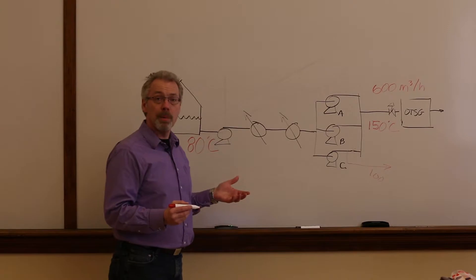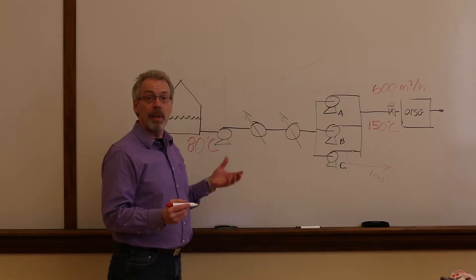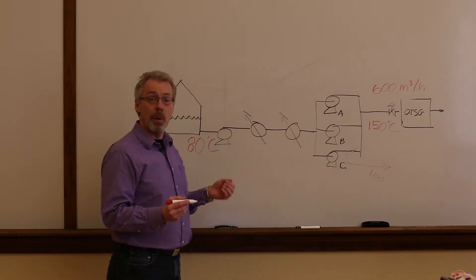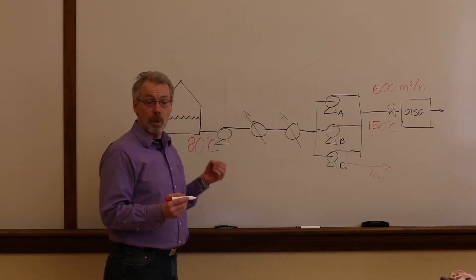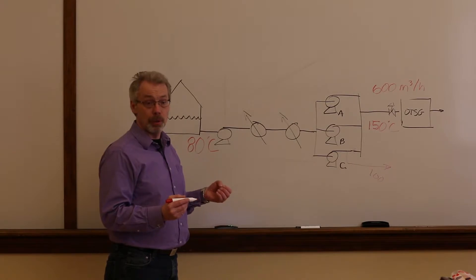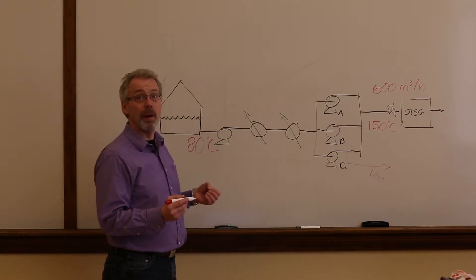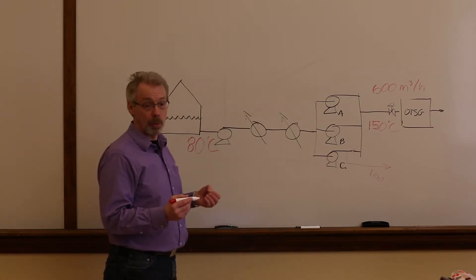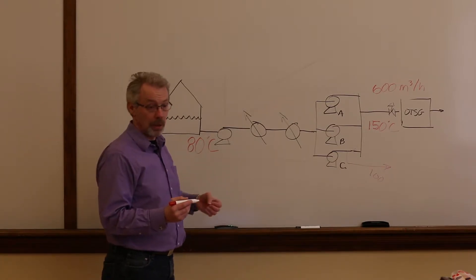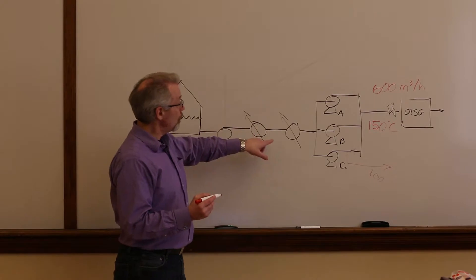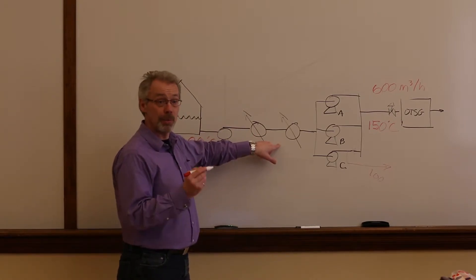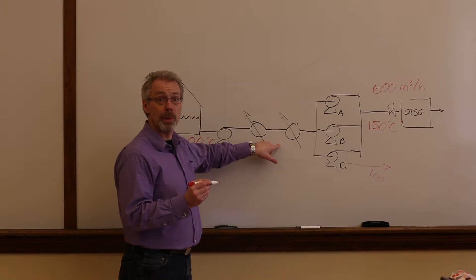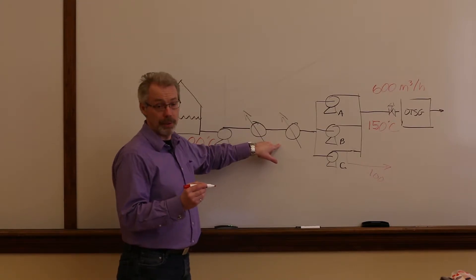So when the third pump is started, there is an extra 100 cubic metres an hour of coolant going through the high pressure pumps, and that 100 is being wasted. The total coolant flow rate through the heat recovery section has now increased from 600 cubic metres an hour to 700.